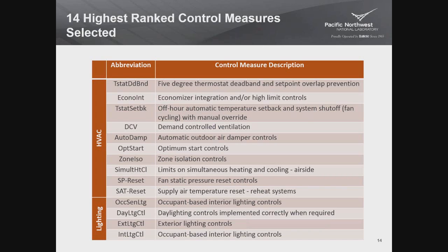Imagine you have a building that's occupancy begins at 8 o'clock in the morning. You've been set back to 55 degrees at night. Obviously, you don't want to just turn that system on at 8 in the morning. People will come into a 55-degree cold building. So one way of doing it is to just start the building at 6 o'clock every morning and start getting it up to speed. Well, that's not allowed by the code.